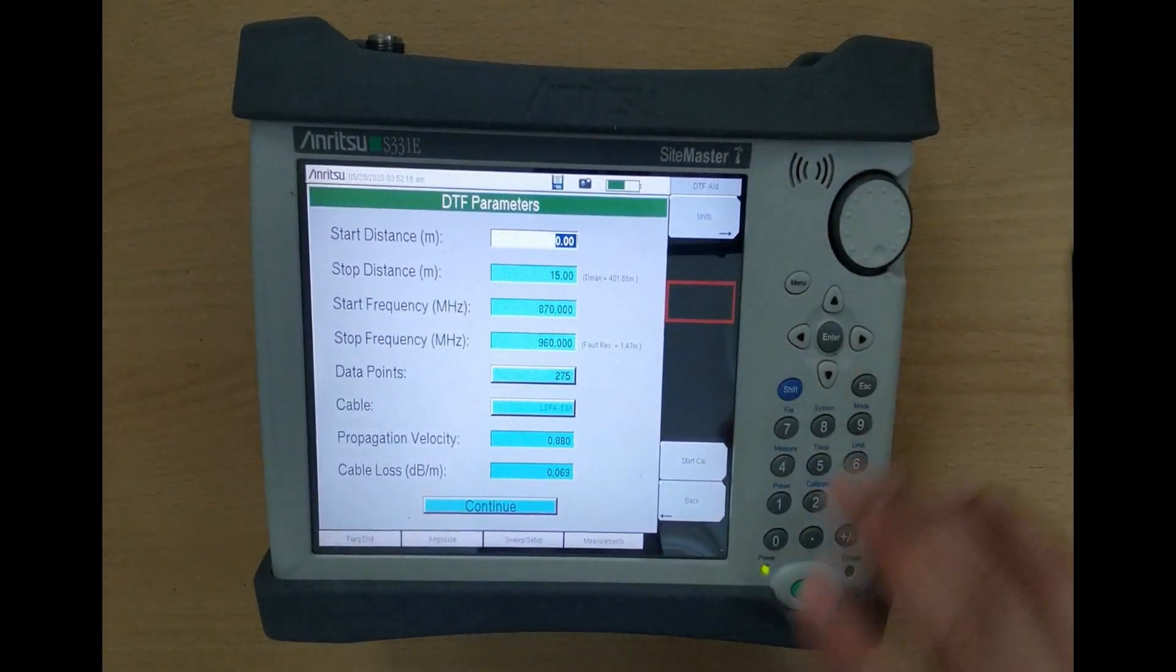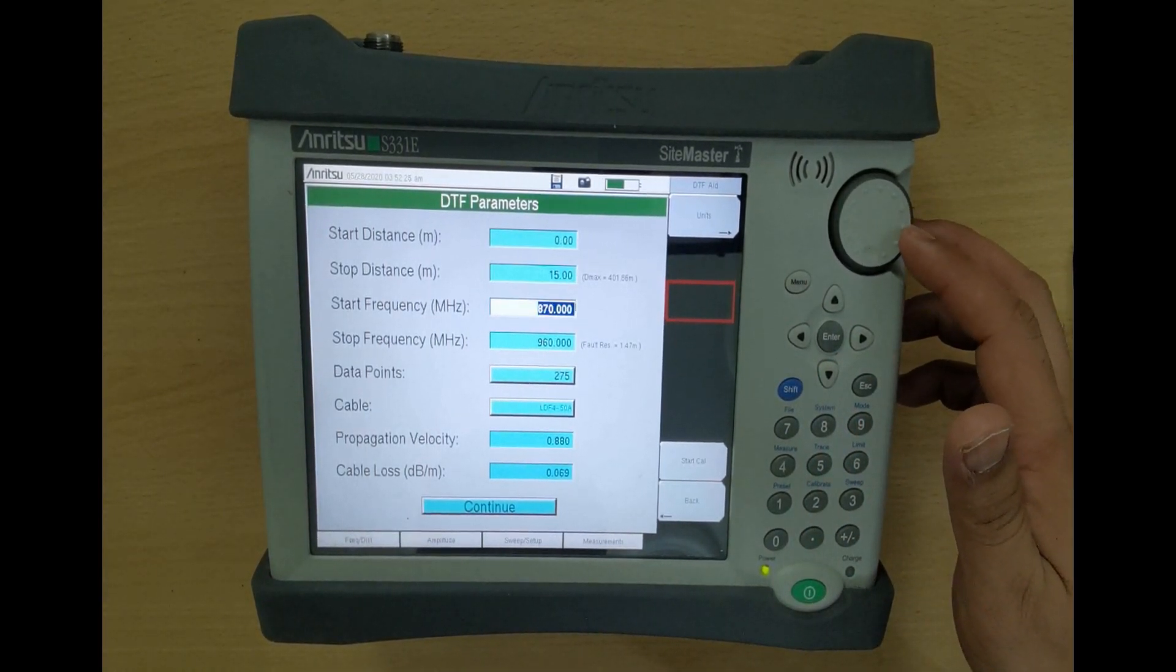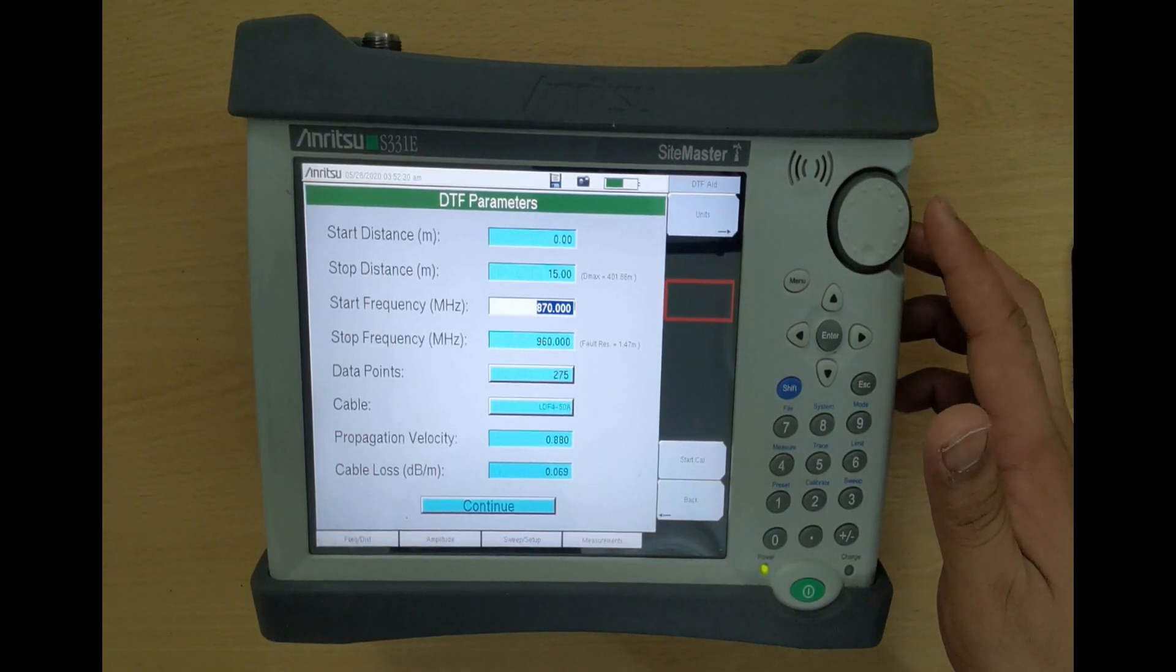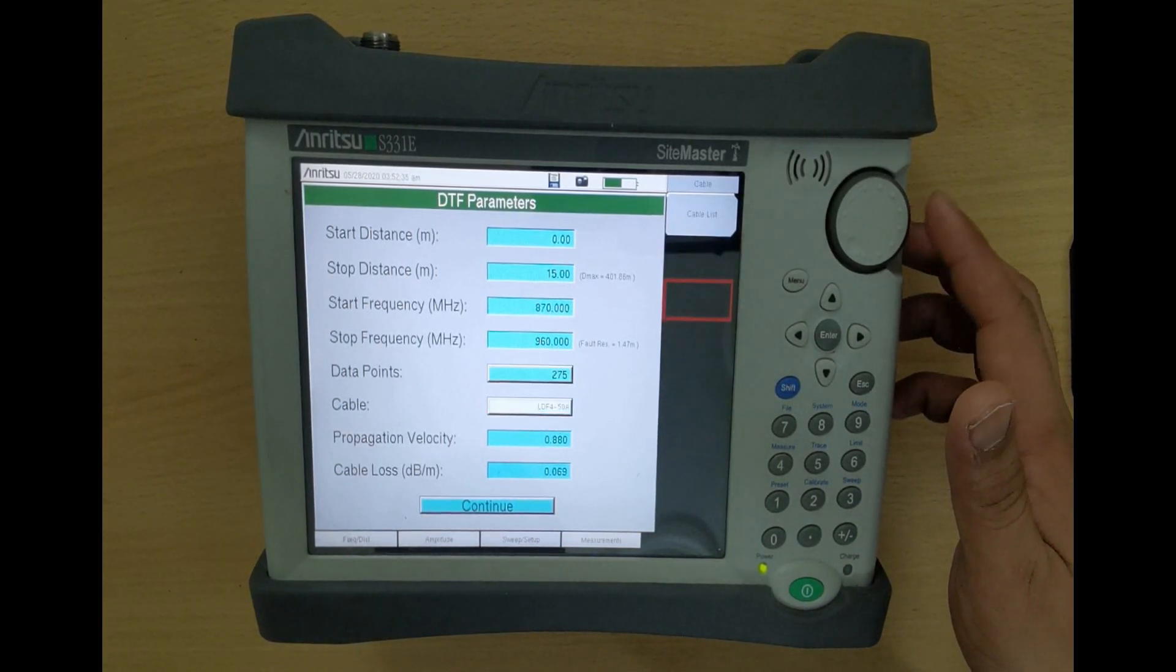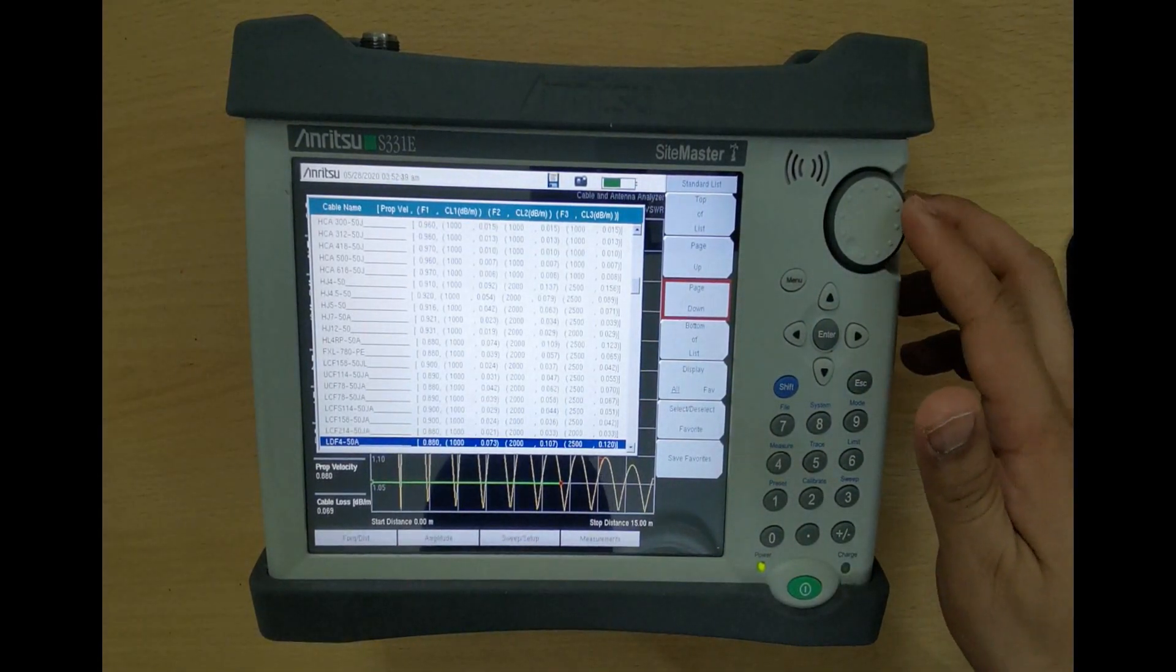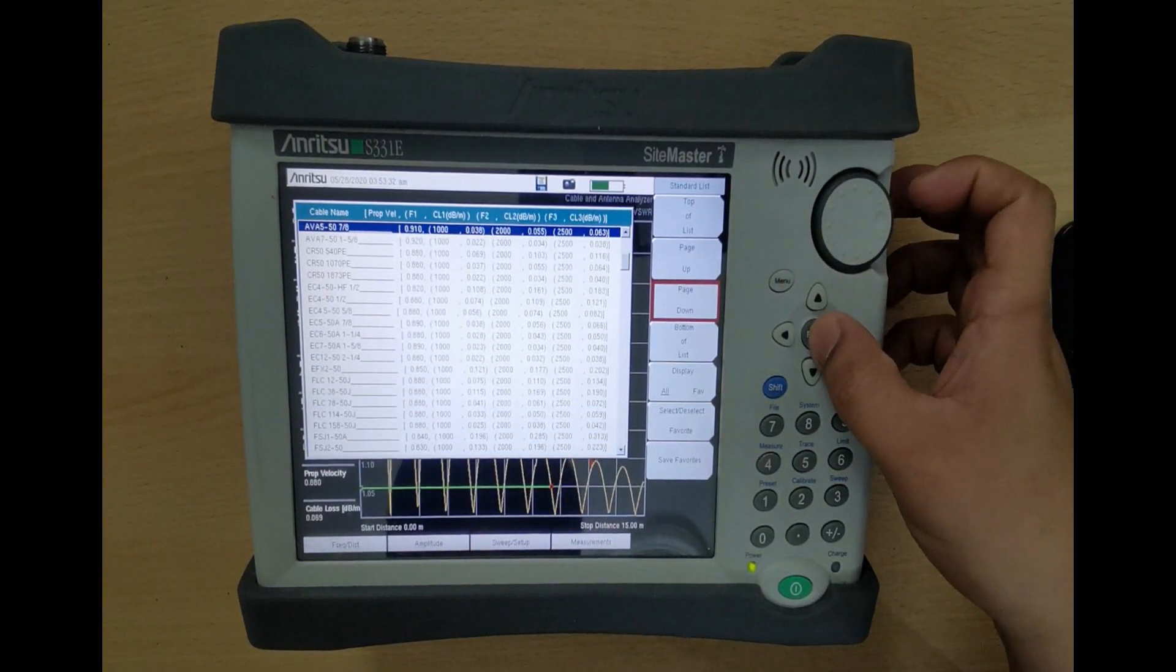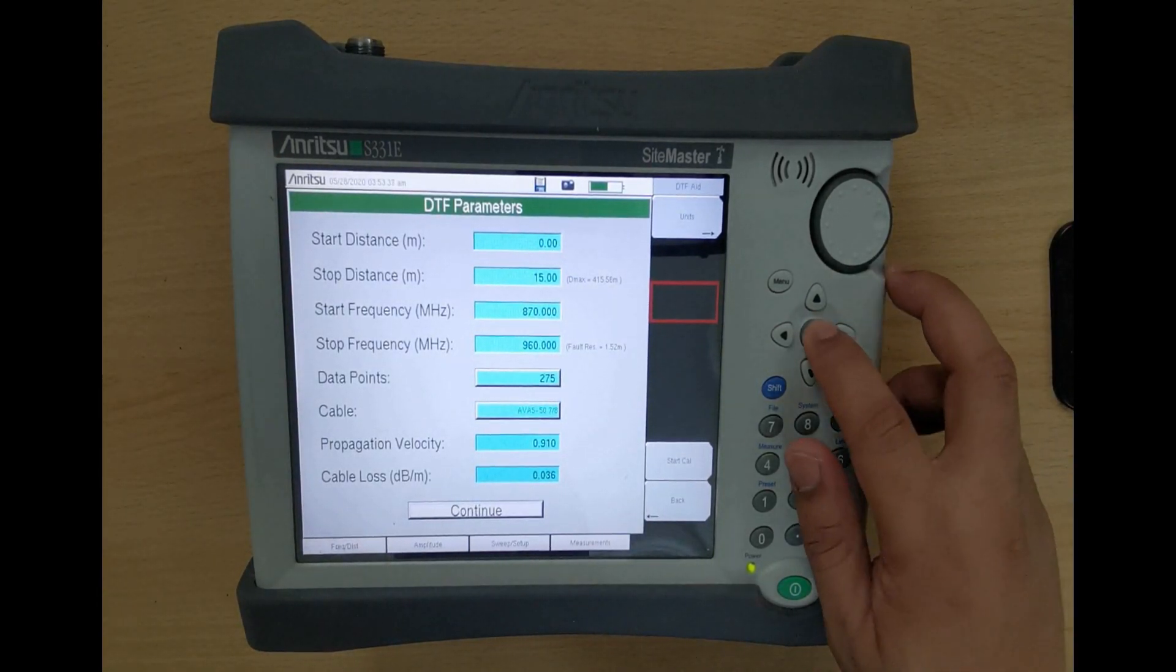You can edit the DTF parameters by turning the circle button, going through Start Distance, Stop Distance, Start Frequency, Stop Frequency, Data Points, and Cable. You can change the cable type by pressing Enter. Locate the correct cable and press Enter.